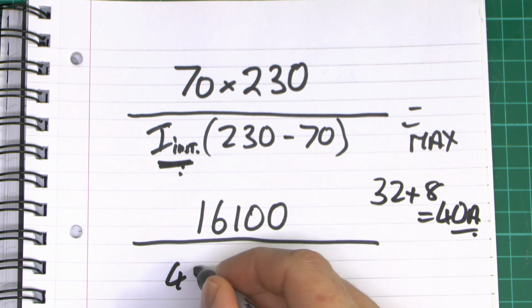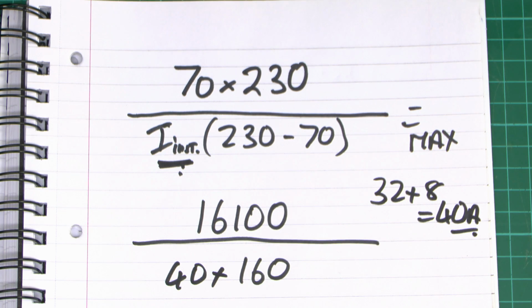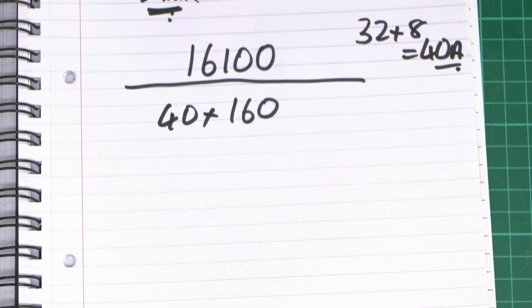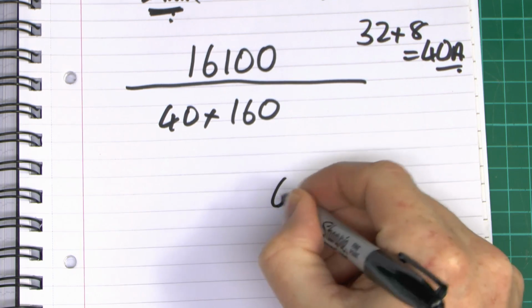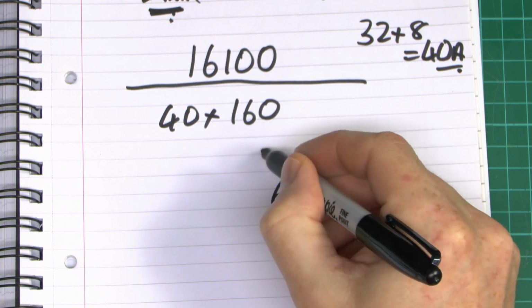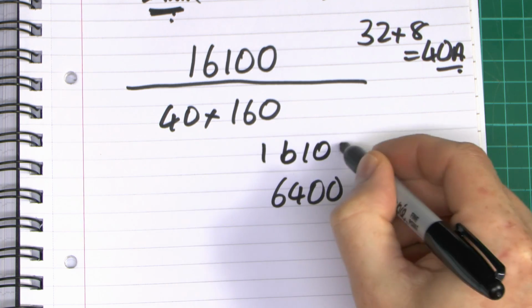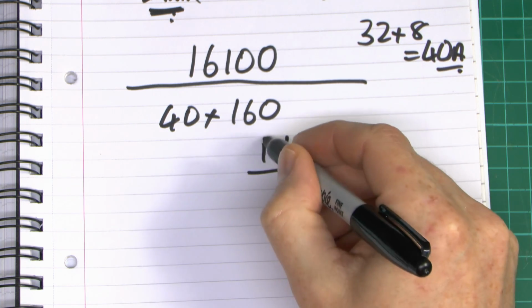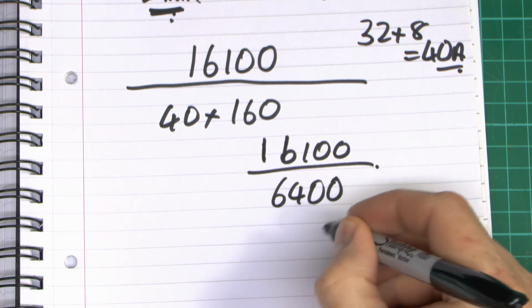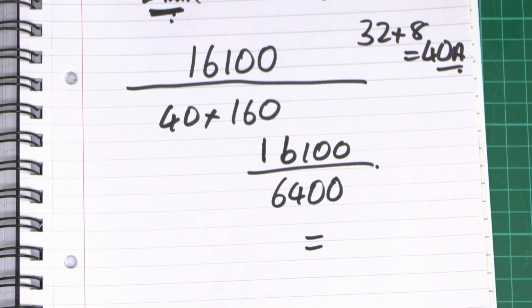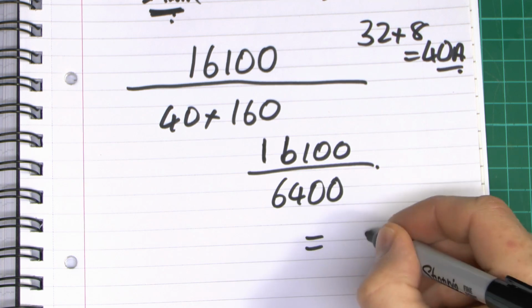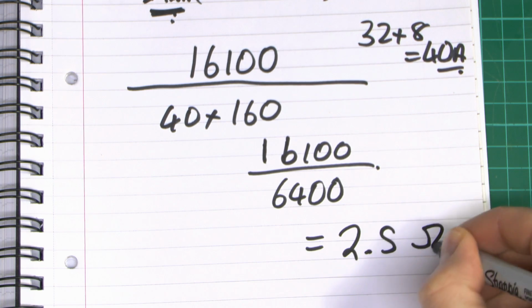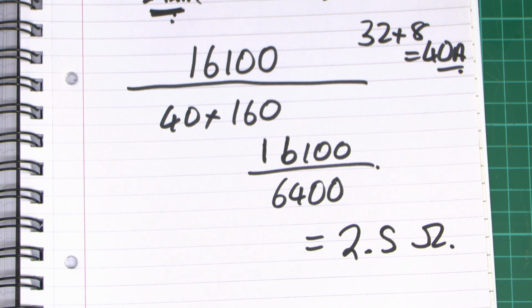So that would be 40 times 160 in the bottom. And essentially what this divided by that is going to be the maximum resistance that we can actually have. So 40 times 160 is 6400, and of course it's 16100 on the top. So 16100 divided by 6400, and the result for our maximum impedance there gives us a result of 2.5 ohms.